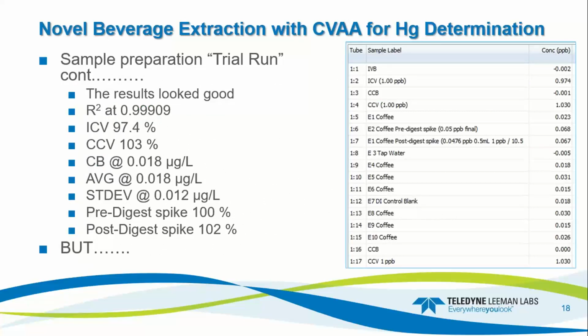So the trial run, the results looked really, really good. R squared was 3 9s and a 0.9. Initial calibration verification came in at 97.4. The continuing calibration verification was at 103%. Control blank was 18 ppt, 0.018 ppb. Average sample at 0.018. Standard deviation was 0.012. And the pre-digest spike was 100%, and the post-digest spike was 102%.